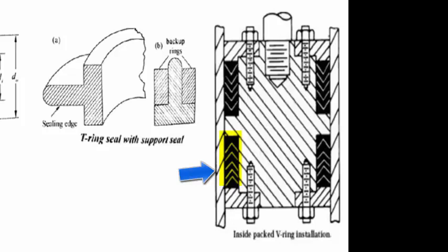So you can see here, all these things are V-ring seals. You are having the V cross section, several V cross sections are there. At the top you are having one specific triangular shape, and at the bottom you are having another special shape of the seal. If the piston length is very, very large and you want the sealing for a very large area, instead of buying one single seal, you can buy the standard seals and keep on adding the different V shapes in between, and you can increase the length of the sealing area. In the same fashion, you can also use the U-shaped seals.